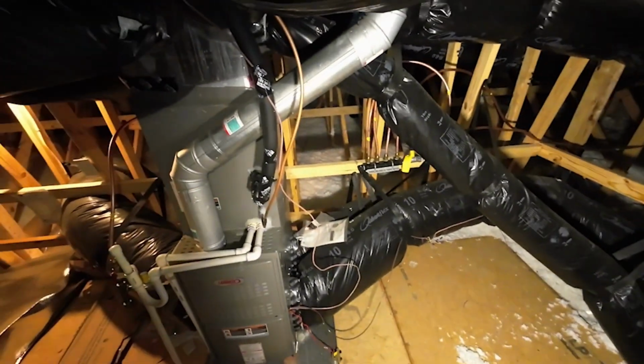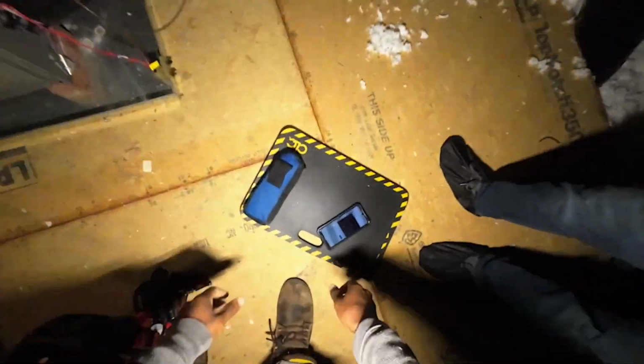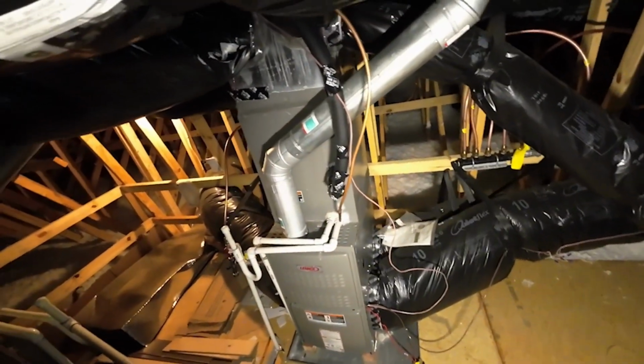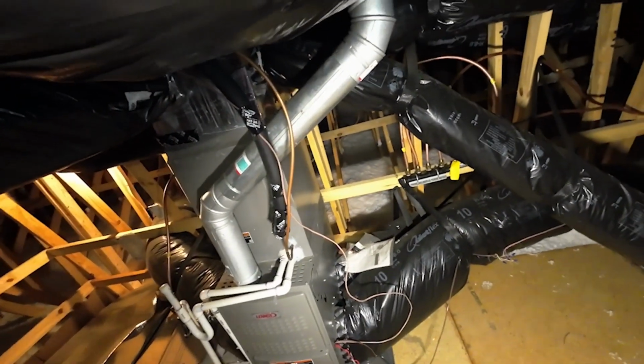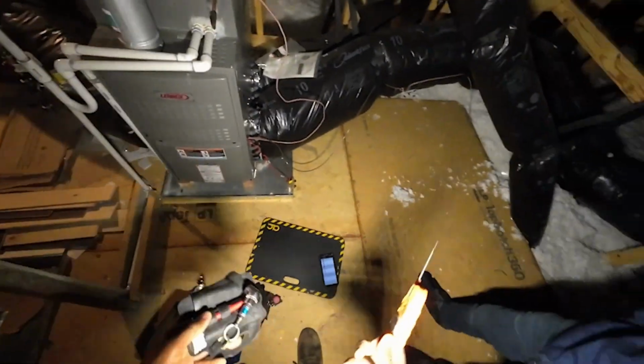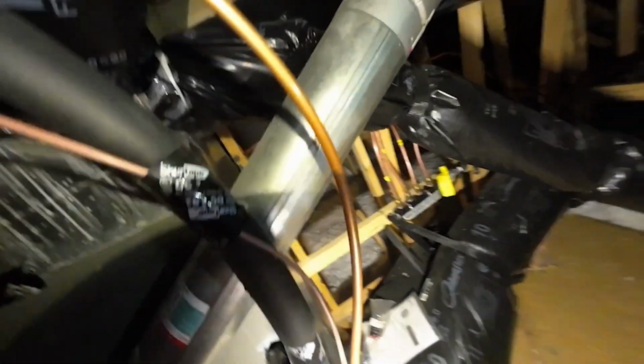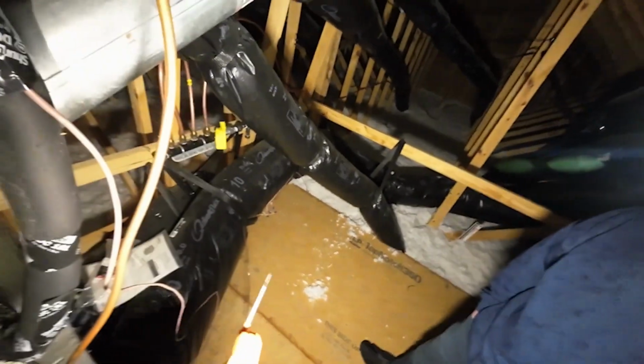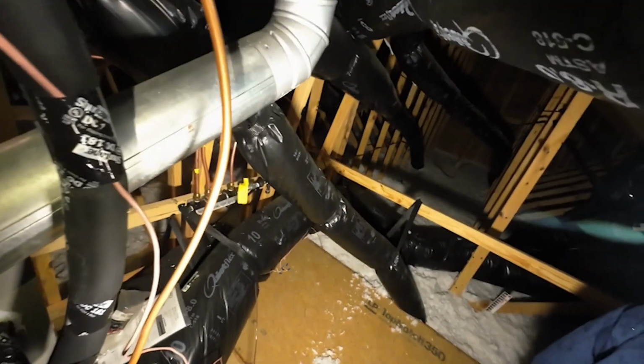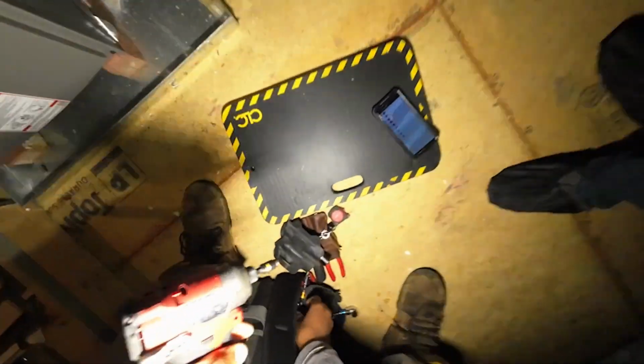exhaust gases. Okay, so the first thing we want to go ahead and do, oh sorry, did you have any questions on that? Because I'm probably going pretty fast. Oh, that's all right. My apologies. Let me know if I'm going a little too intense, because I like to use this here. You could just use a regular K-type. I don't know if you take any of these type thermometers on you in your bag, but hit it somewhere in like one of the takeoffs. Preferably not in the flex, because that could cause the flex to tear internally. I know you did a little bit of duct work and you saw the lining. If you put a rip in that lining, if the static pressure is high enough, it could tear it. Use like a screw. Well, I'll just use my little drill bit. You can just cover this back up with tape. Put a tiny hole there, you know.